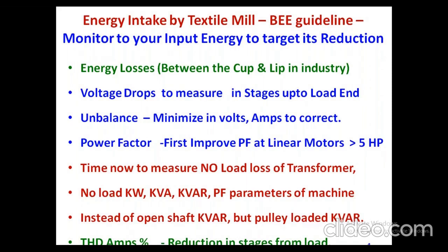By switching on and off, what is happening? By switching a capacitor on and off on a T connection to a given motor, what is the kVA drop and what is the kVA rise without the capacitor? The demand from the motor. See, the T connection will say whether the capacitor is effective on the motor. All the linear motors where there is no VFD, any motor needs to be fitted with a capacitor and an MCB, and the capacitor is checked every month to know whether it is functioning okay. If a 25 kVA capacitor takes only 32 amps, or it is taking less than 25 amps, it means the capacitor has already derated and its life is out.